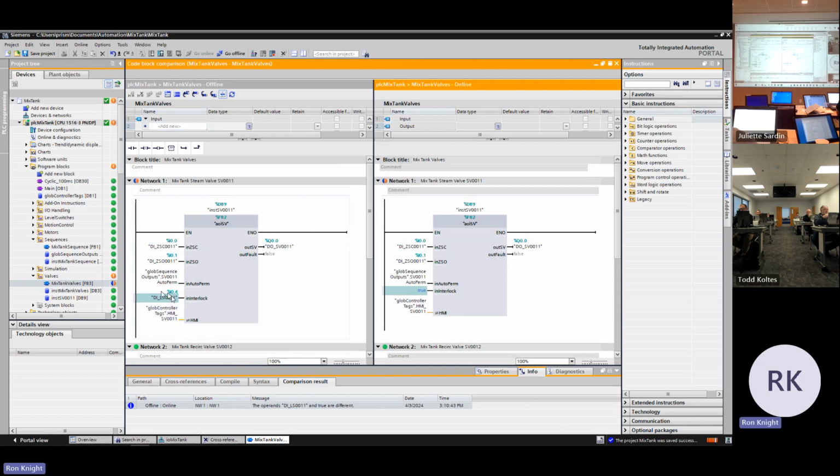All right, so what's offline is our lid switch. What's currently running in the PLC is a hard-coded true. So over the weekend, the lid switch must have failed. They didn't feel like fixing it, so they just said, they need to run, I'm just going to put true here, and they can take care of it Monday. But we need this. This is a safety issue. I really don't want to leave it with a hard-coded true on my interlock.